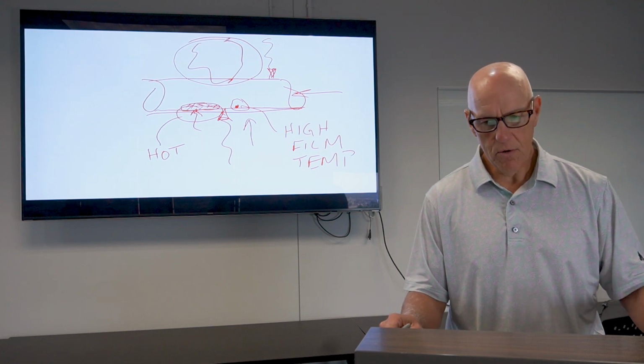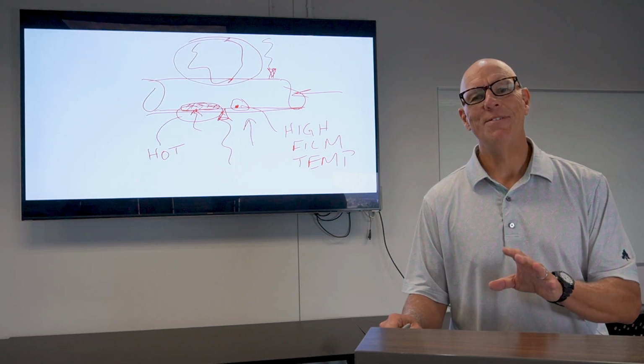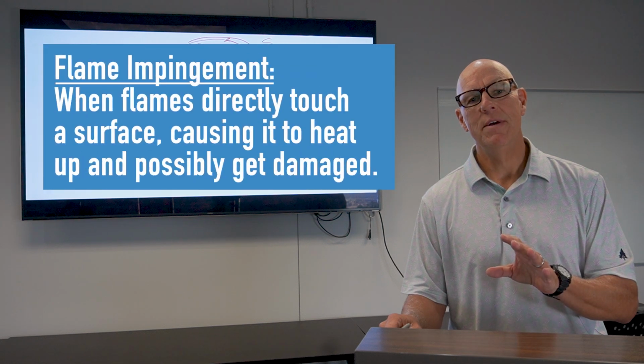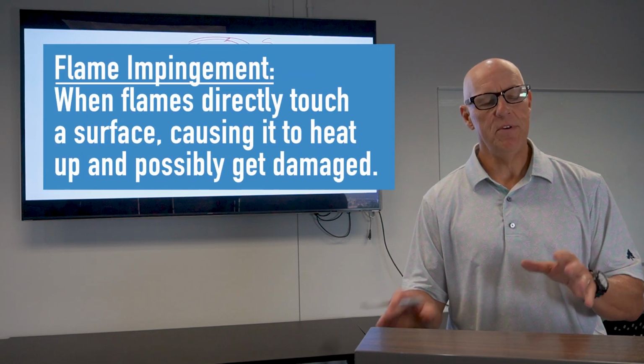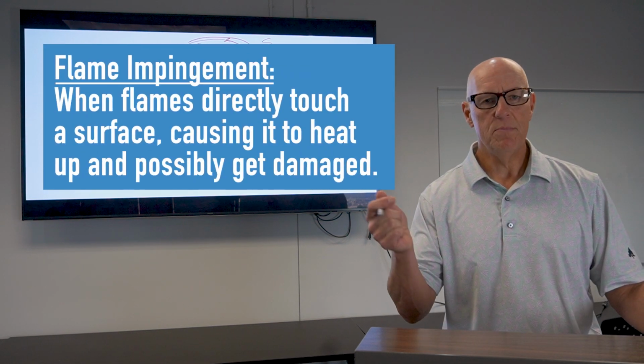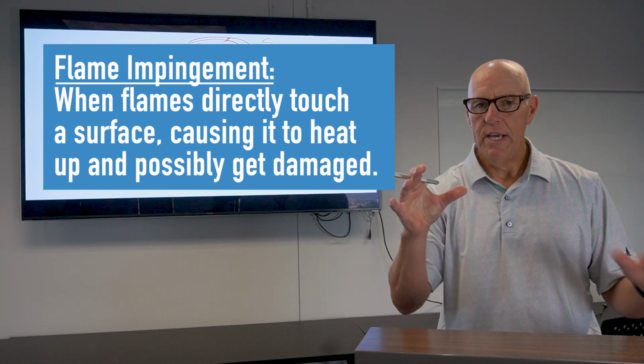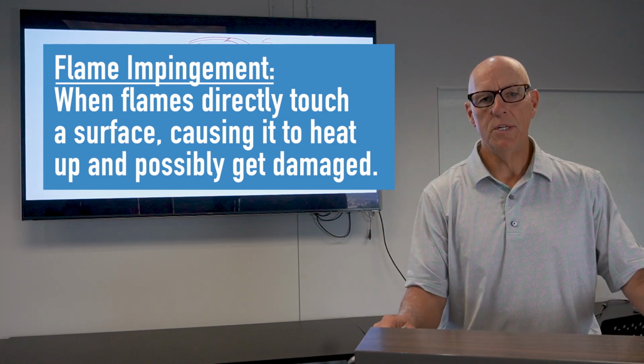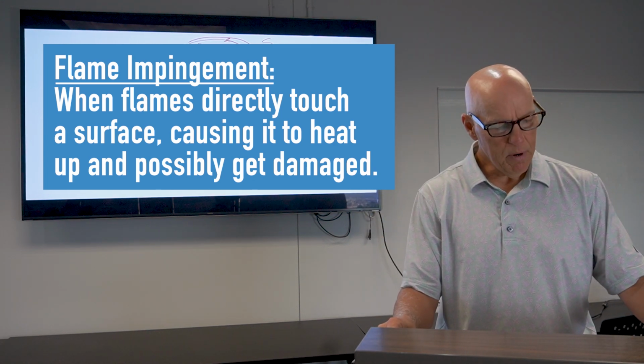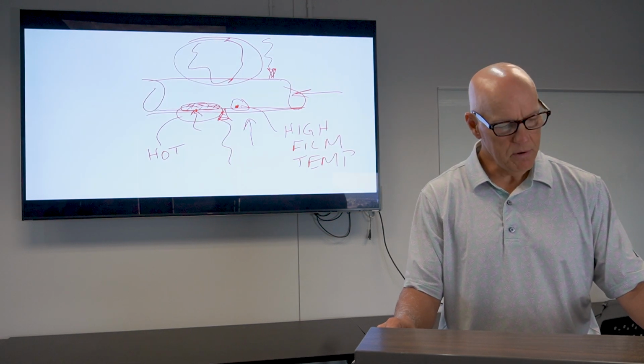So in general, you don't want to have flame impingement. That's a good indication. If you look in a heater, you open up the sight door, you're looking in. If you see flame on a coil, it's probably not a good thing, and you're probably going to have premature failure of that coil.